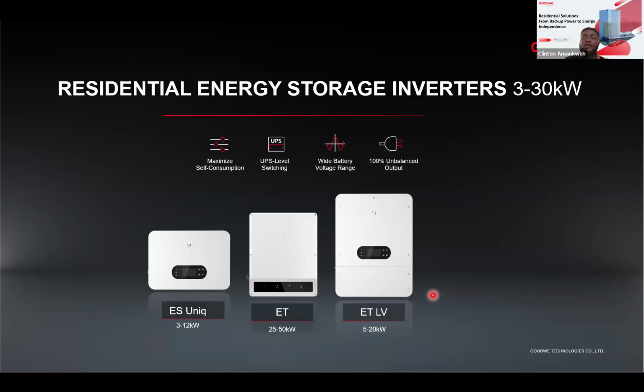With this, in less than 4 milliseconds you can seamlessly switch from on-grid power supply to backup power supply, and you get a wide battery voltage range. Our low voltage inverters range from 40 to 60 volts, even though it's a 48 volt, 51.2 nominal volt battery. So for battery voltage range, you have 40 to 60 for low voltage, and 200 to 800 for high voltage.